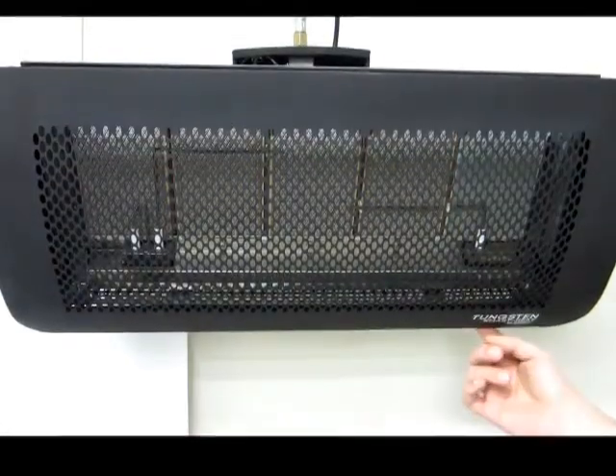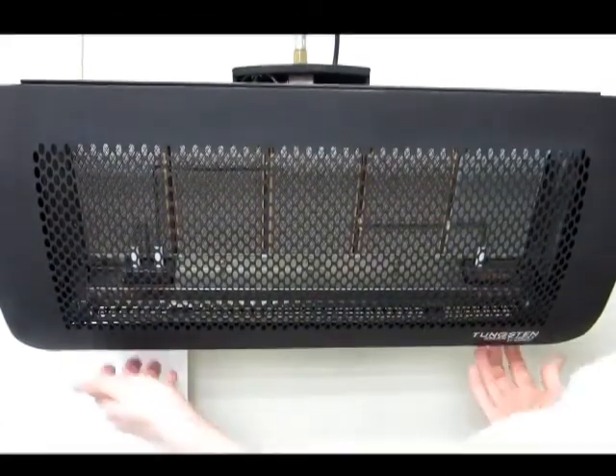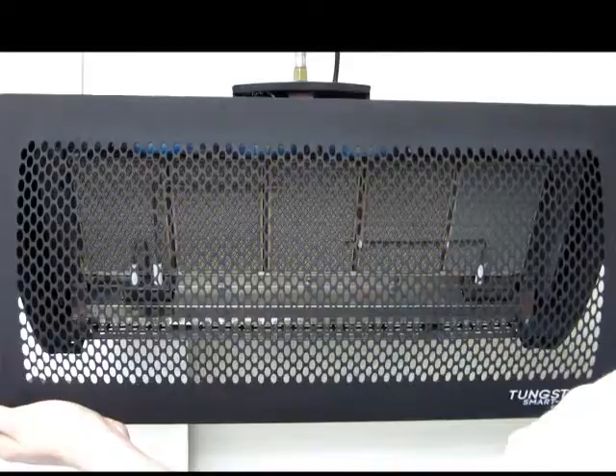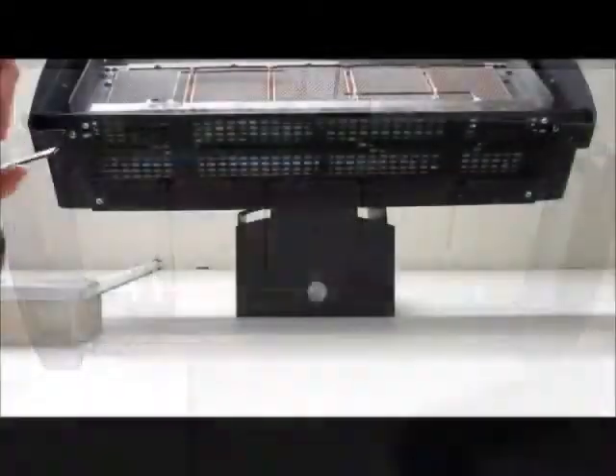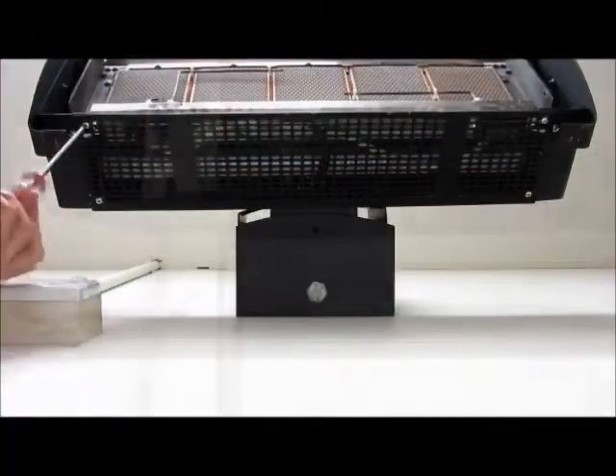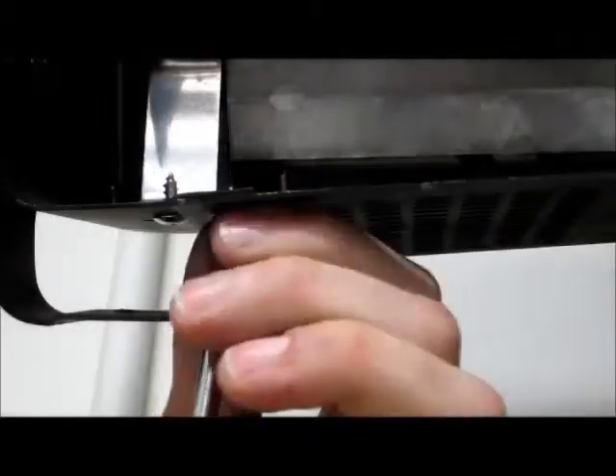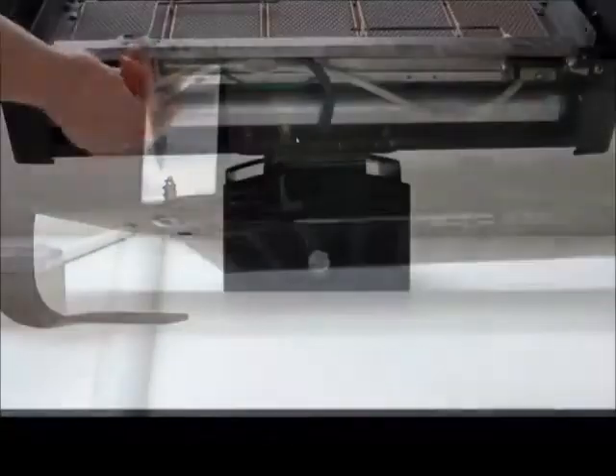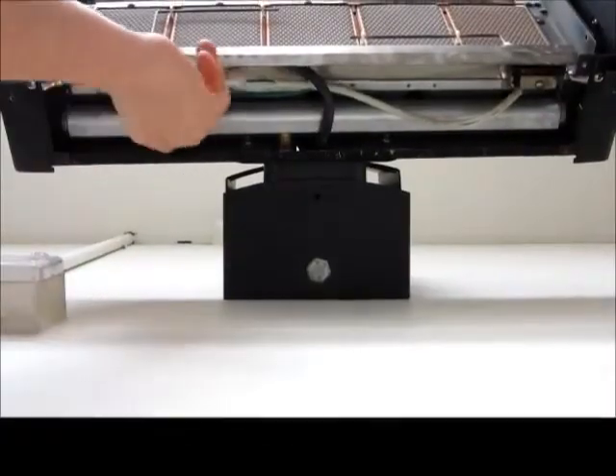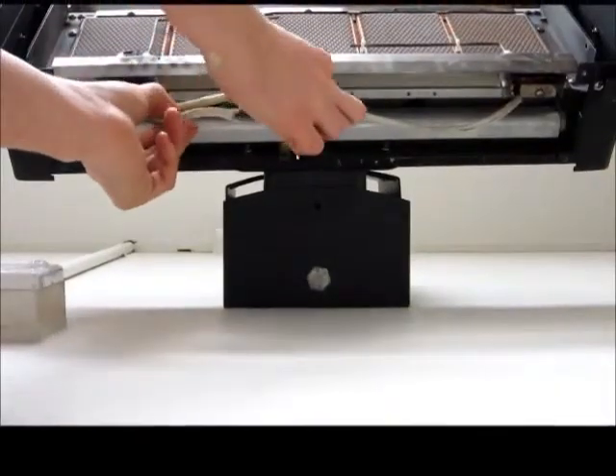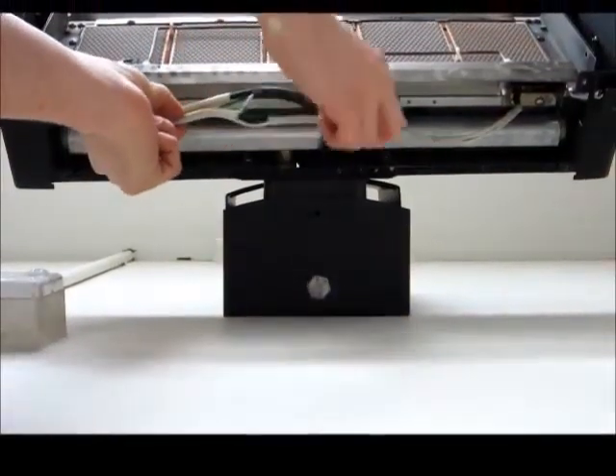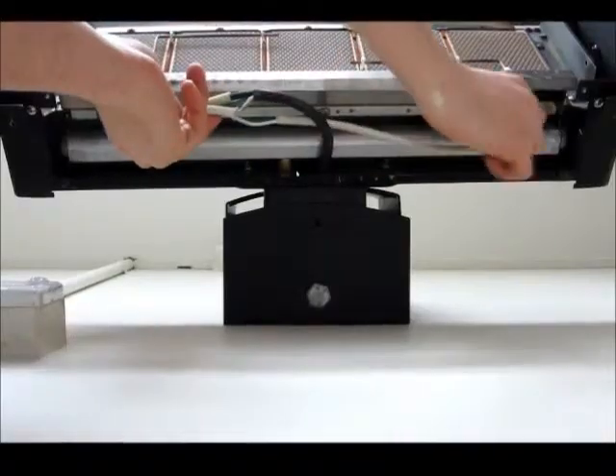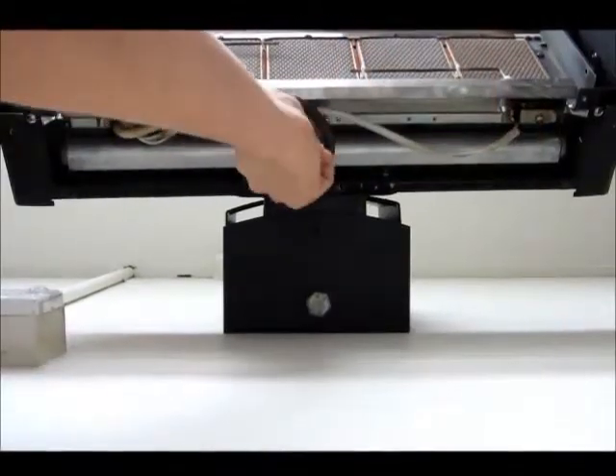For the tungsten units, remove the front cover of the heater by removing the 2 mounting screws and sliding the base of the cover forward. Next, undo the 4 base cover screws to remove the base cover, revealing the wiring harness. Inspect the cabling to ensure that the wire insulation is complete and that there are no breaks that may be earthing out on the unit. Also ensure all terminal fittings are securely in place on the body of the heater.